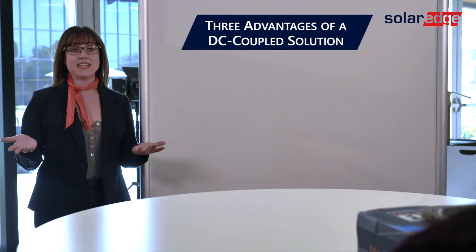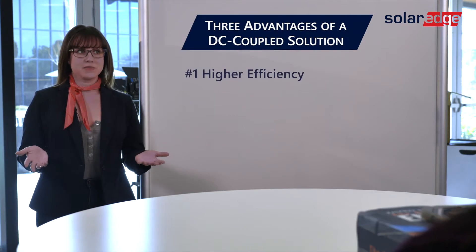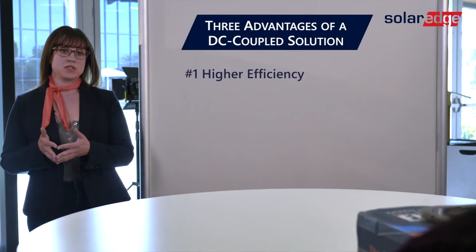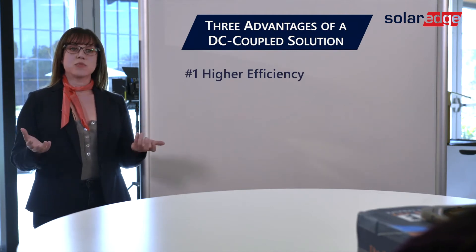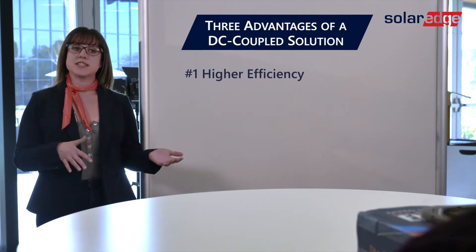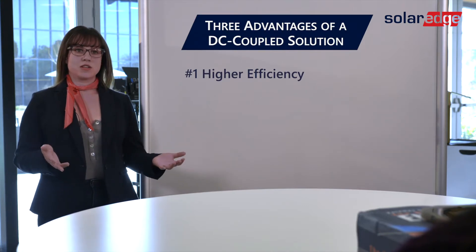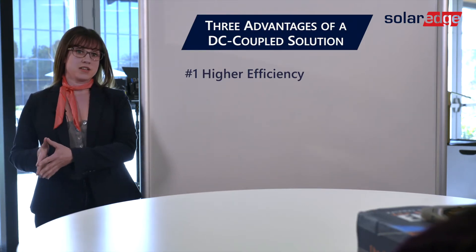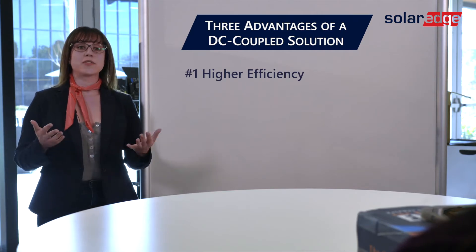There are three advantages I emphasize when talking about the advantages of a DC coupled solution. Advantage number one: higher efficiency. But why is that? What actually happens in an AC coupled solution versus a DC coupled is really the difference in the number of conversions we have of the energy. In a DC coupled solution — our SolarEdge solution — you only have one conversion of energy. In an AC coupled solution, you have three.